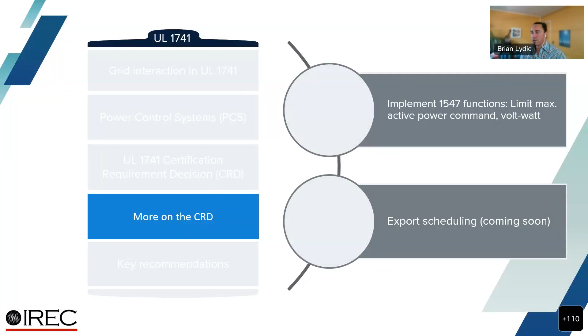The key recommendations in the batteries report relating to 1741 are mostly focused on this power control systems CRD. For one, we'd like to ensure that power control systems are appropriately addressed in procedures — in the interconnection rules — basically to allow the use of them for export limiting. Those procedures should require certified power control systems. There could be allowances for non-certified power control systems, because you might have systems or inverters with other components from differing manufacturers, which might make it hard to get certified. But utilizing certified power control systems makes it a lot easier to put this through a more simplified review process.